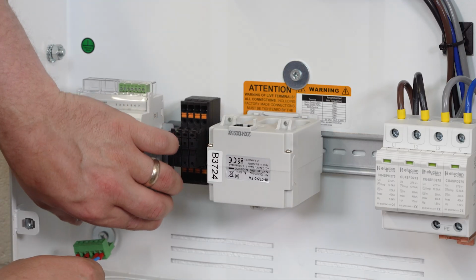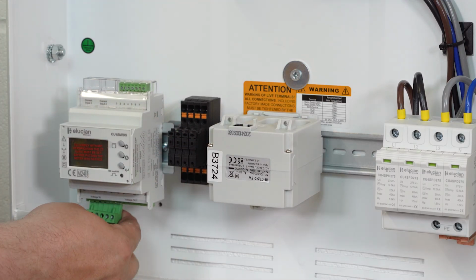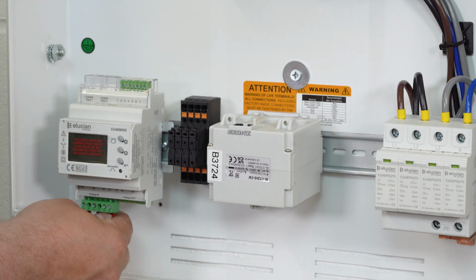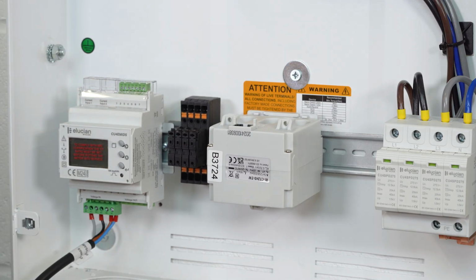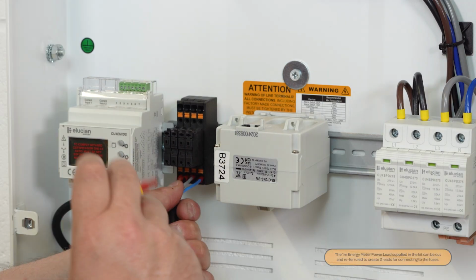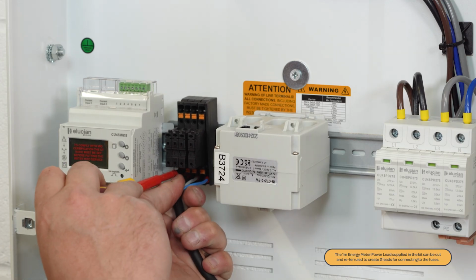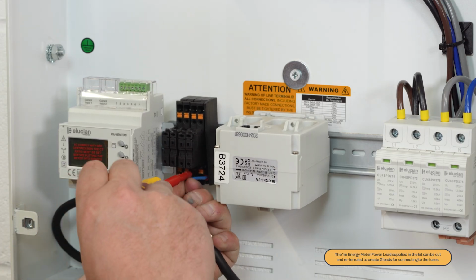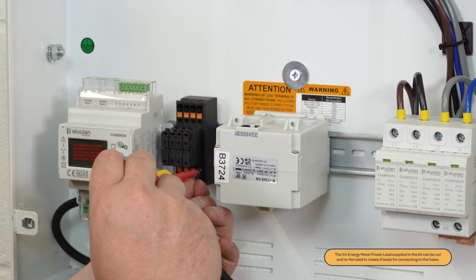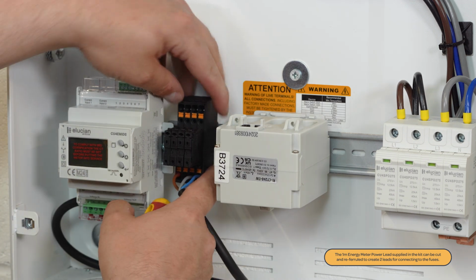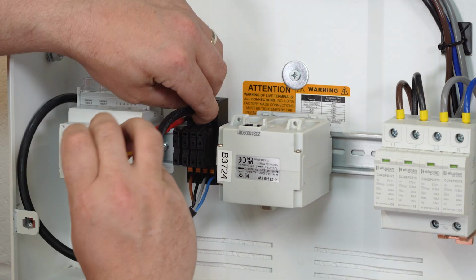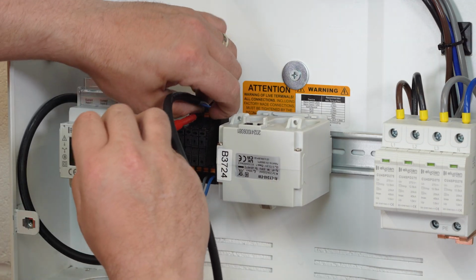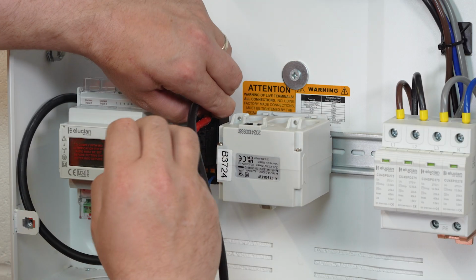The pre-fitted plug on the energy meter power lead will need to be connected to voltage in located on the left underside of the energy meter. The ferruled conductors on the other end of the power lead will need to be connected into the L1, L2, L3 and neutral push-fit terminals on the fuses. Attach the energy supply cables into the top push-fit terminals on the fuses.